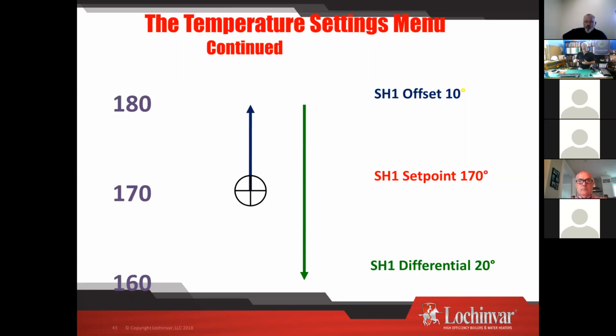Or maybe I don't want to overshoot as much, or I want to allow my boiler to overshoot more. Want to give it more landing strip and runway. So, for example, I run my boiler here at my house very, very cool. And then I run like a 20-degree offset. What that does is it gives my boiler room to idle. Its goal is once it crosses that set point, I'm going to be at an idle, but sometimes in a very low load condition, even at the minimum firing rate, that boiler's still going to kind of creep up. So if you give it a little more room to run, it'll keep it from shutting off and then coming back on again. So again, you can set them for whatever works for you.